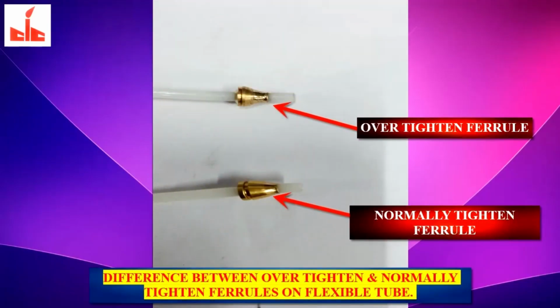Difference between over-tighten and normally tighten ferrules on flexible tube. Over-tighten ferrule looks pinched and partially blocked. It can restrict the pressure of the gas. So don't over-tight the nut.